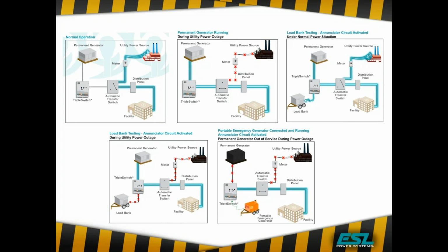So here's a panel layout that you can see, again, showing that during normal operations, when you lose utility power, you're going to automatically feed right to your facility. It also shows when you're doing a load bank test, what happens if you lose utility power during a load bank test, and then hooking up your portable generator. Are there any questions about the functionality of the triple switch?